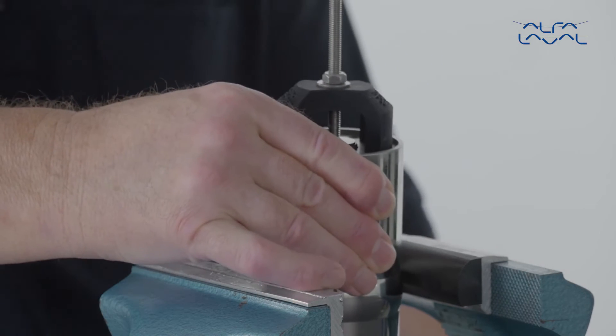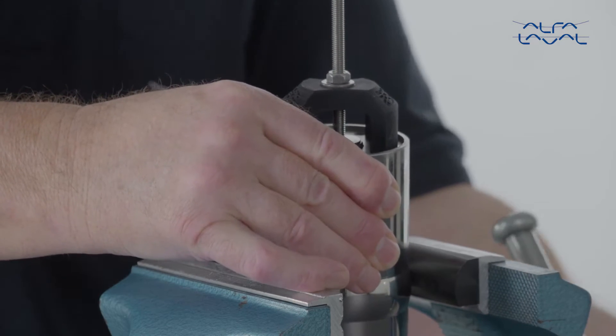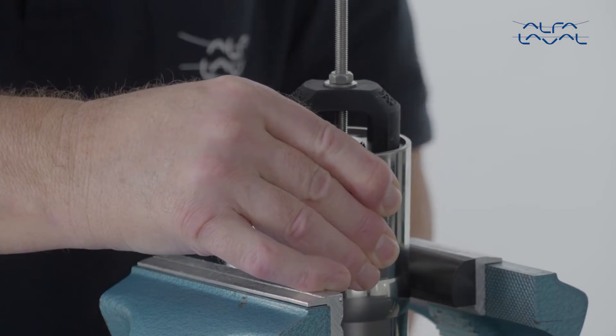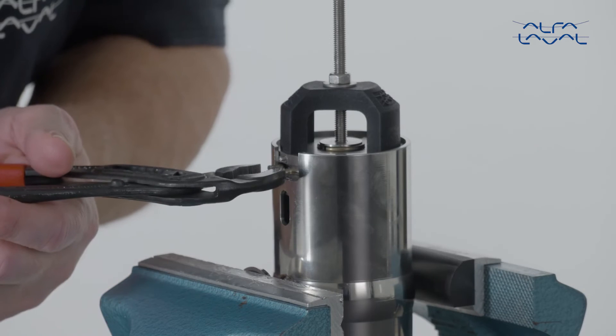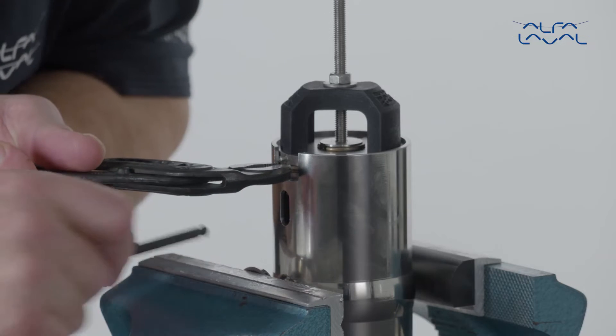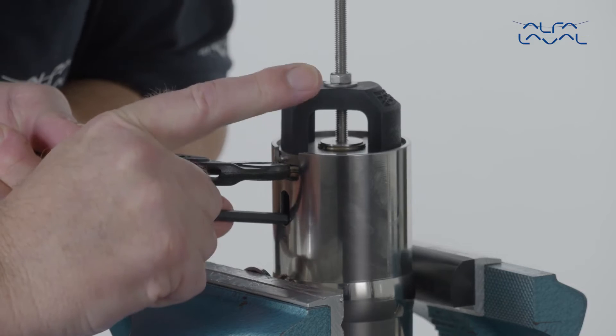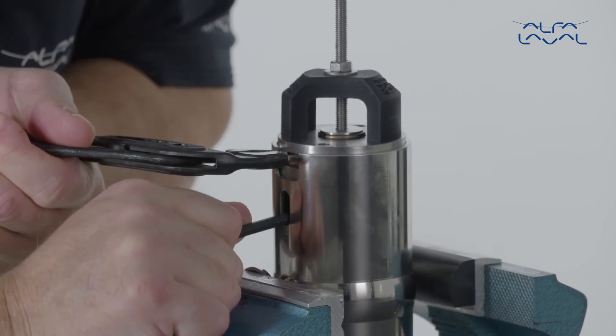Place the assembly in a vise. Use soft jaws to avoid scratching the surface of the PlusClean. Using pliers, squeeze the ends of the retaining ring. Insert an Allen key in the hole on the piston to lift the assembly slightly.